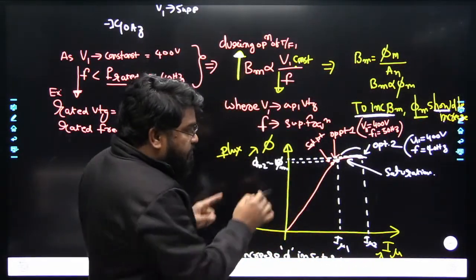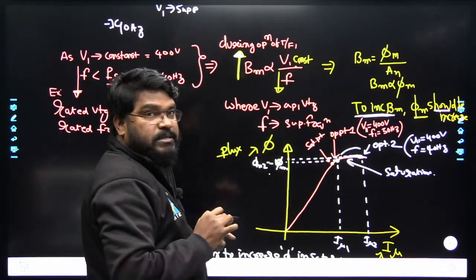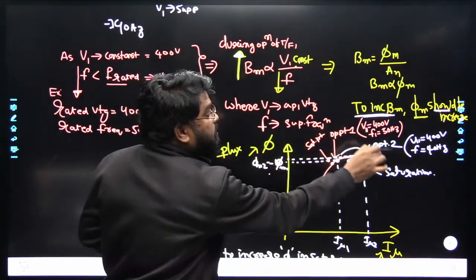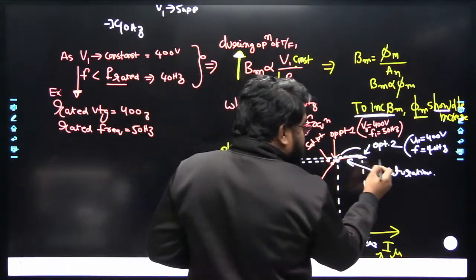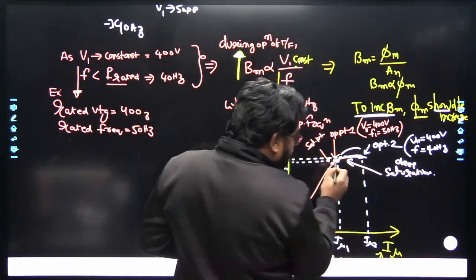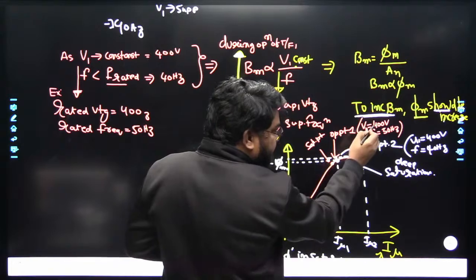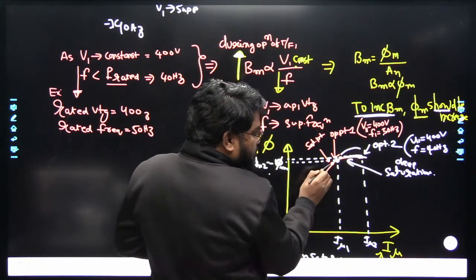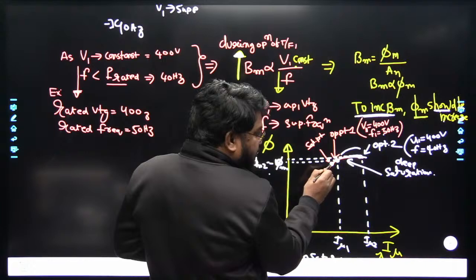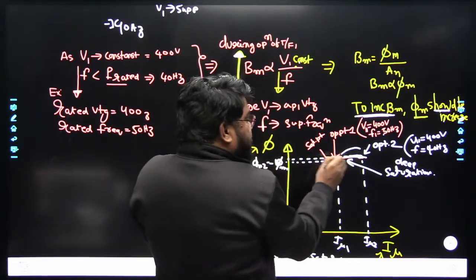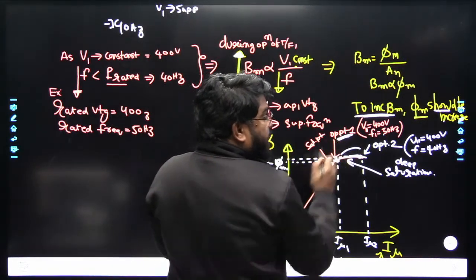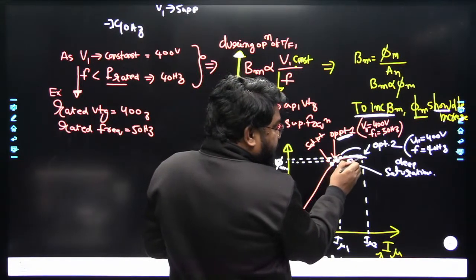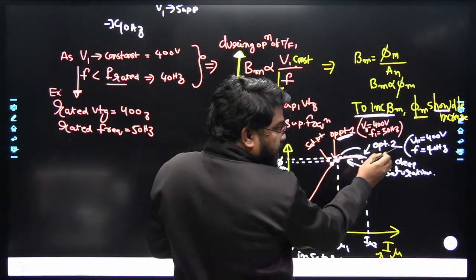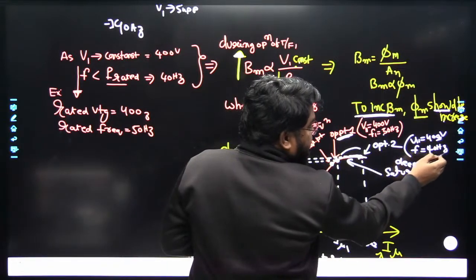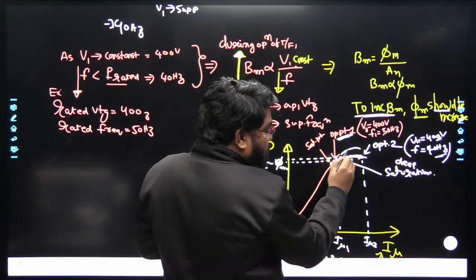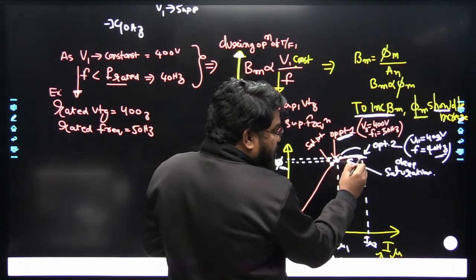So to increase phi maximum in the saturation region, the transformer core goes into deep saturation. Deep saturation means, here initially if it is operated at rated voltage and rated frequency, this is just above the saturation point, this is operating point 1. Suppose if it is operated at the same voltage but less than rated frequency, the operating point shifts to this point.